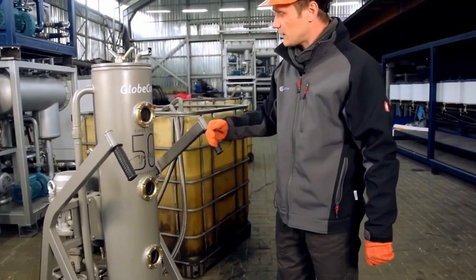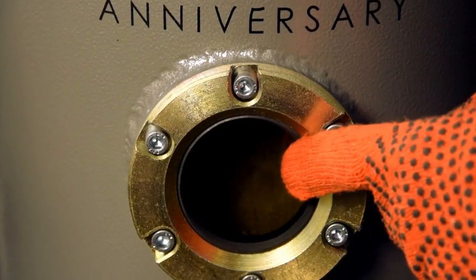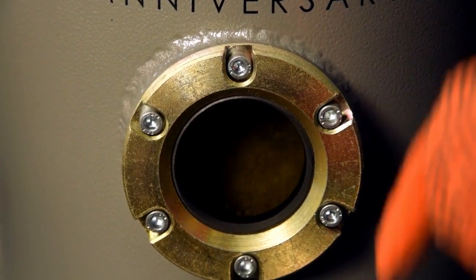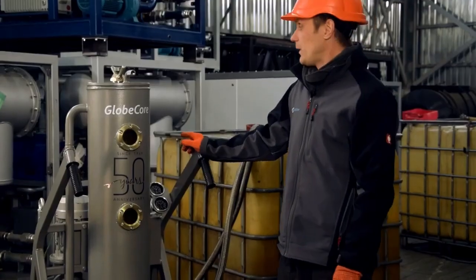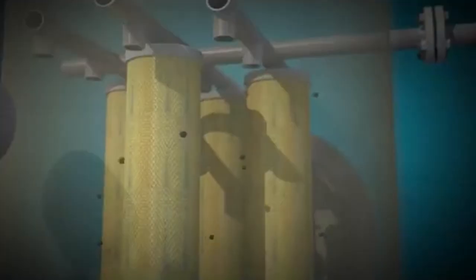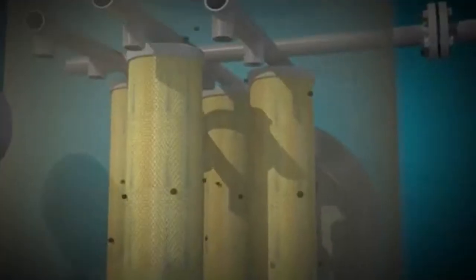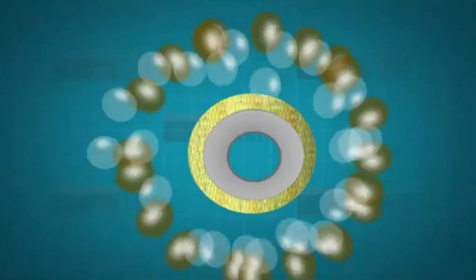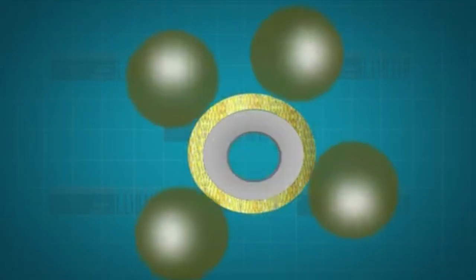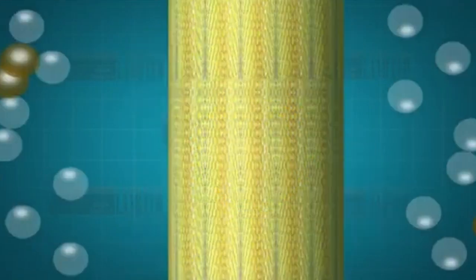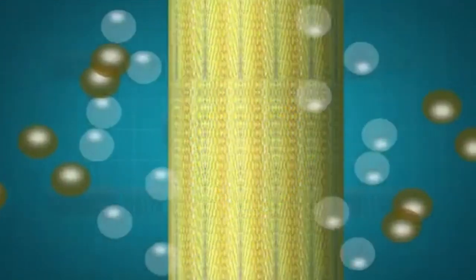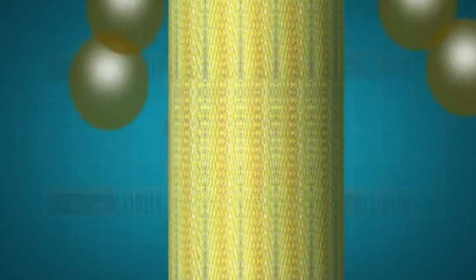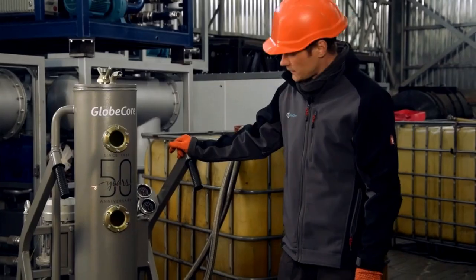The CMM-1CF machine removes solids through coarse and fine filters, and water through a coalescing filter. The use of a coalescing filter allows purifying even particularly water-cut oils with a water content of up to 50 percent, which is best suited for turbine oils.